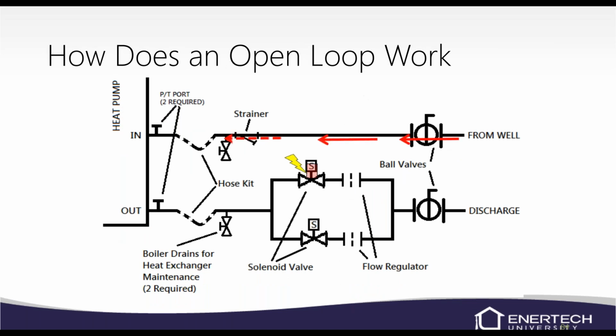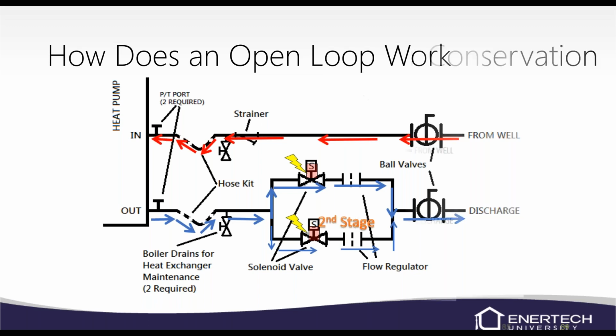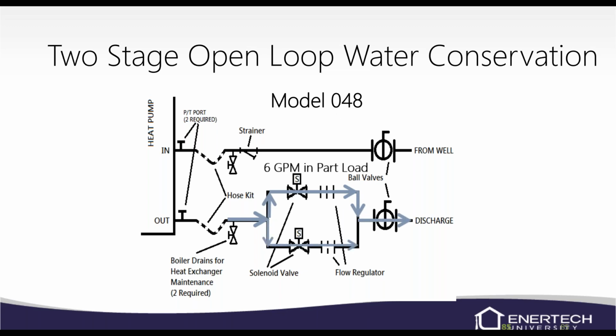So how does an open loop work? Basically a Y1 call is going to open up the Y1 solenoid valve and send that Y1 water flow through. When second stage is energized, Y1 will still be energized, so that solenoid valve is going to be open, and the second one will be open. So then you'll get your total flow back to the system with both solenoid valves open. So on a 048 and part load, we're going to be running roughly 6 GPM. You can actually go a little bit less than that. And then normally in first stage, we're running 2/3 capacity. So we want 2/3 of the flow going through your first solenoid valve and flow restrictor. So you get a 6 GPM flow restrictor for first stage and a 2 GPM flow restrictor for your second stage. So when they're both open, we output 8 GPM.